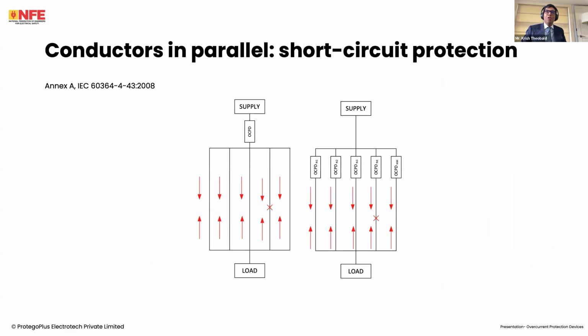Now, it gets particularly interesting when we look at short circuits, and I'll tell you why. Normally, in a short circuit, disconnection occurs and the circuit is dead. However, if there's a short circuit over here, current will not only flow from this side to the short circuit, even if this is just the line conductor, current will also flow back from here, because current going from here will return like this, like this, like this. So you have current flowing from all directions. That's something interesting that happens.